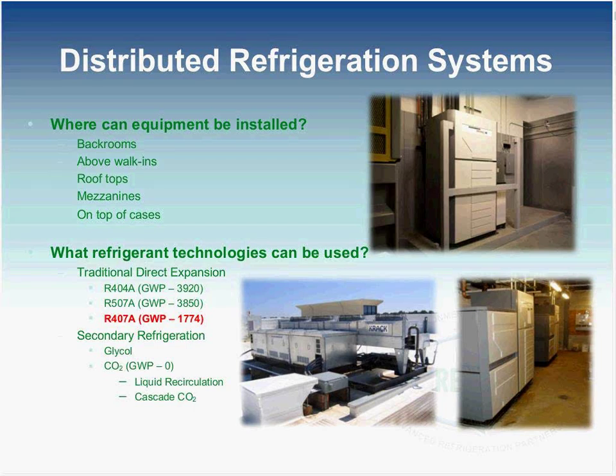Travis, just to maybe clarify for some people that aren't as familiar with these technologies. In terms of, you know, you're walking through a supermarket just as a regular consumer, the traditional system, all the refrigeration equipment is somewhere in a back room, and then the refrigerant has to be piped to every single case that's out in the supermarket that you get your cold or frozen goods. The difference here is that you won't see it, but you're standing in front of the ice cream, and right up on the roof, right above those ice cream coolers, is that freezers have their own little refrigeration unit sitting up there, and the piping goes right from that on the roof, right straight down to the cases, so you're cutting down on the piping an awful lot, right?